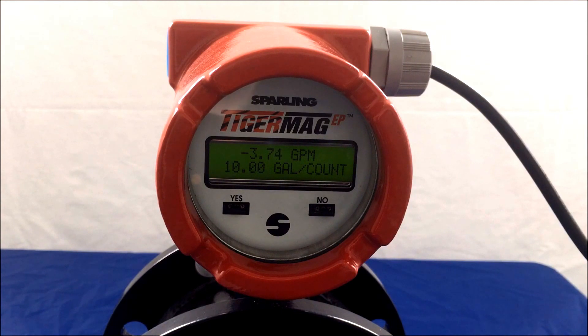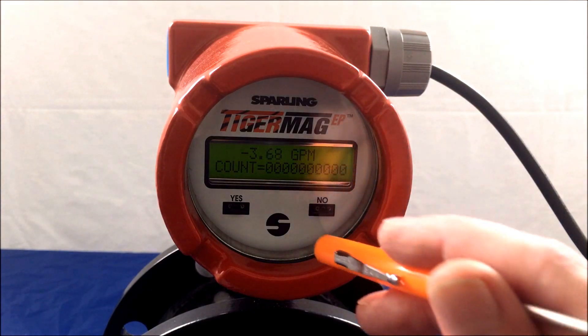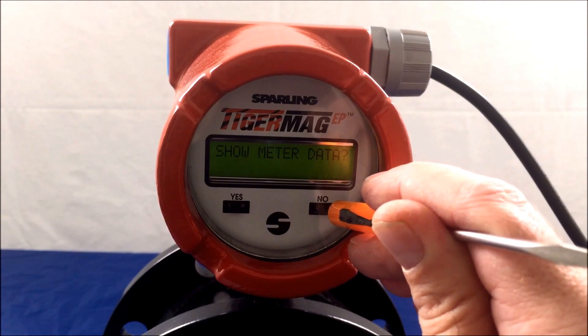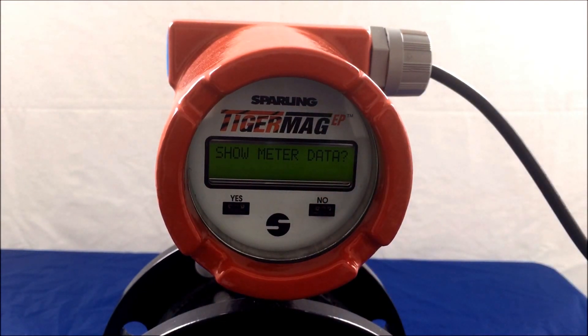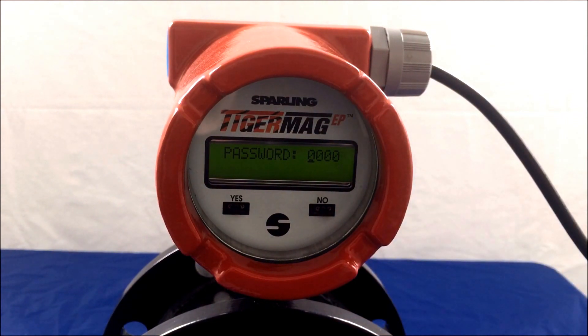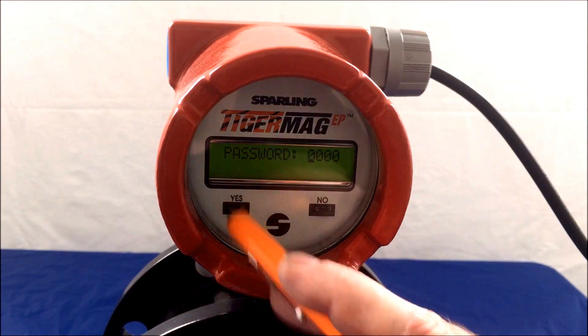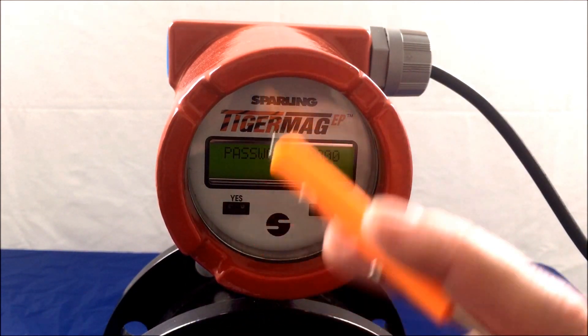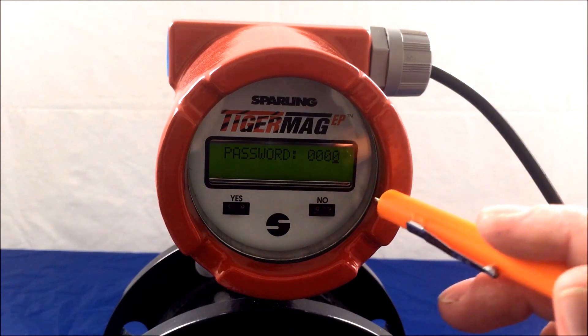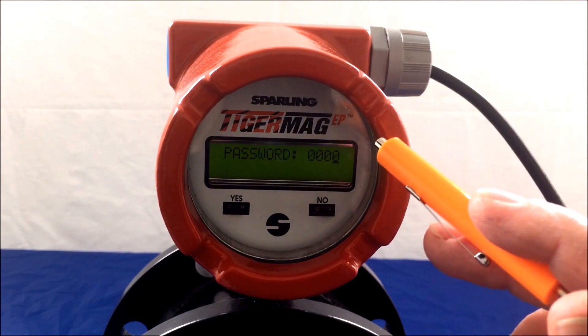Next, after observing the parameters, we will go into the program and observe user selectable setup. Hold the MAG command probe over the NO side for approximately 5 seconds and show meter data will appear once again. This time, hit NO to implement a password. In order to enter a password, YES moves the underscore over to the next digit and NO will increment that particular digit. The default password is 0001.